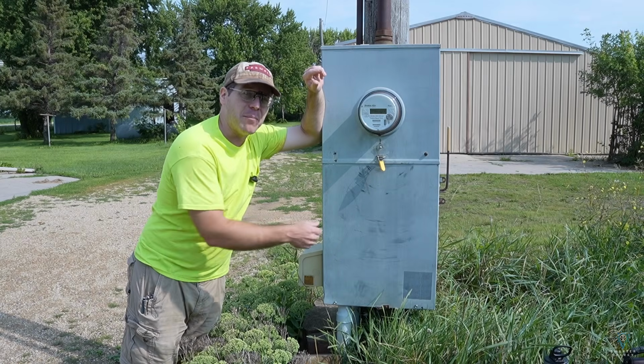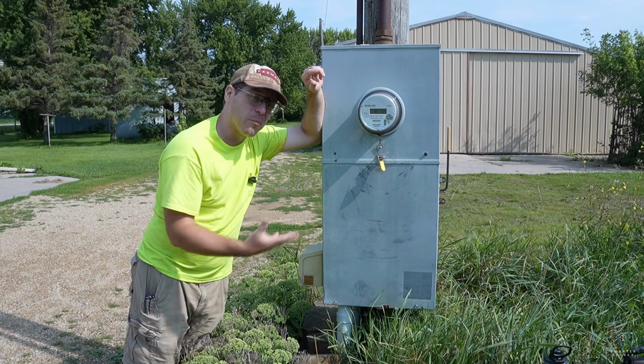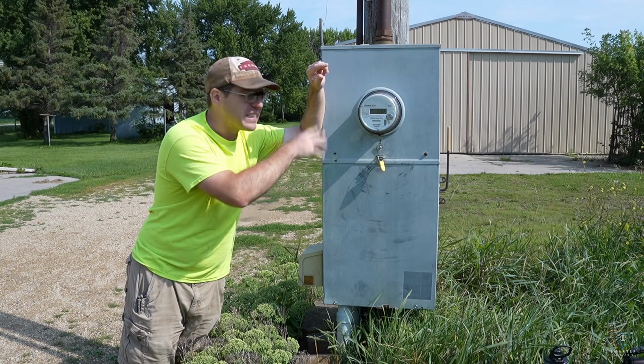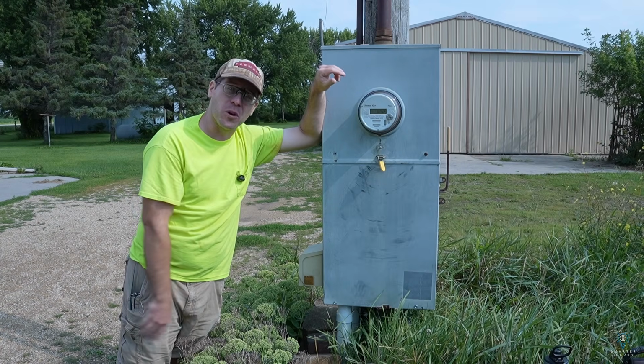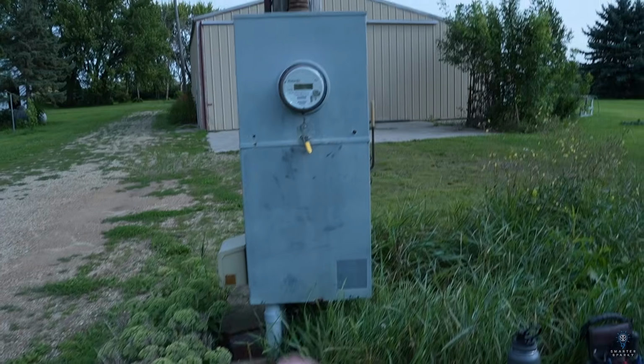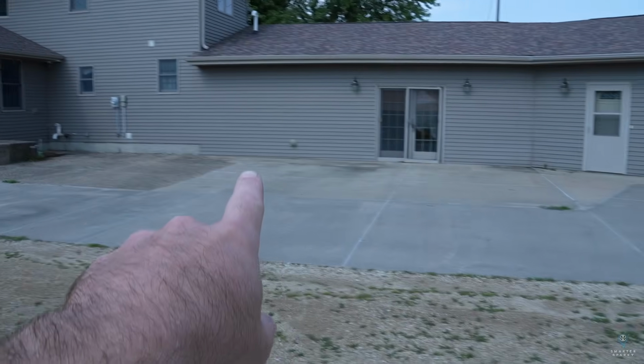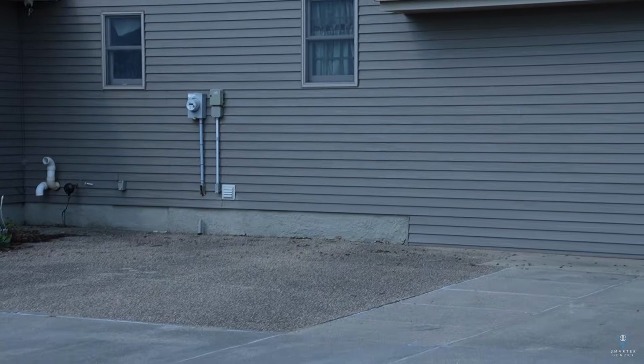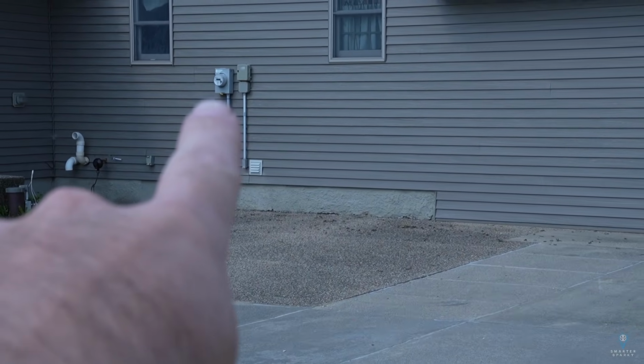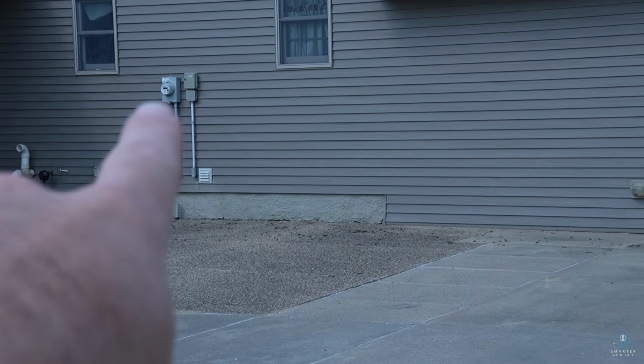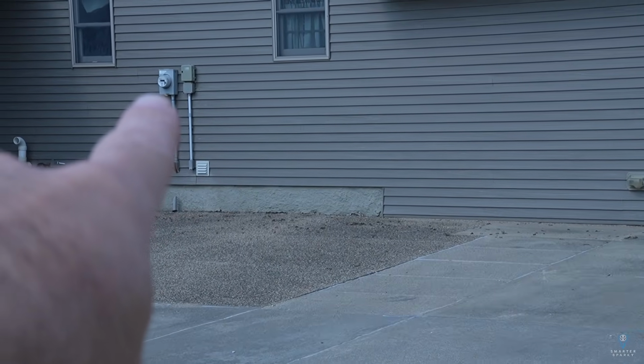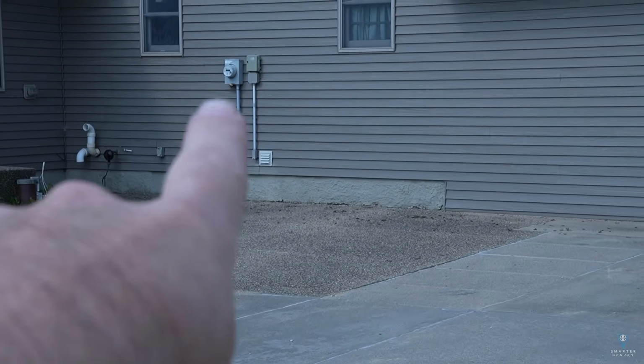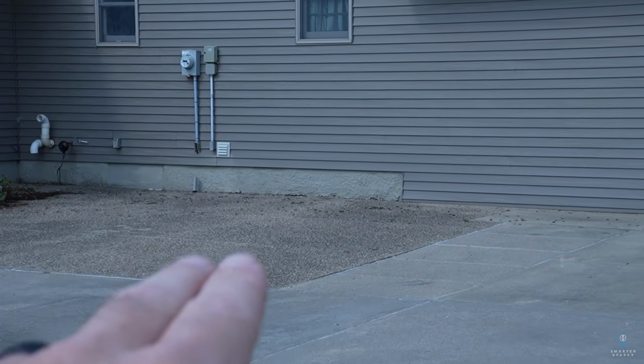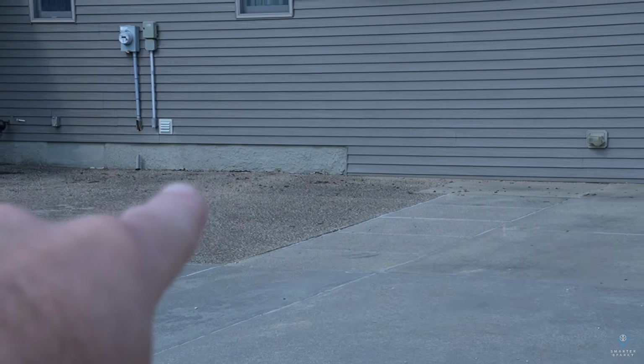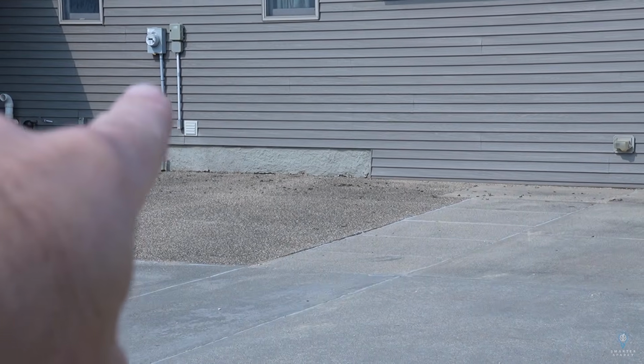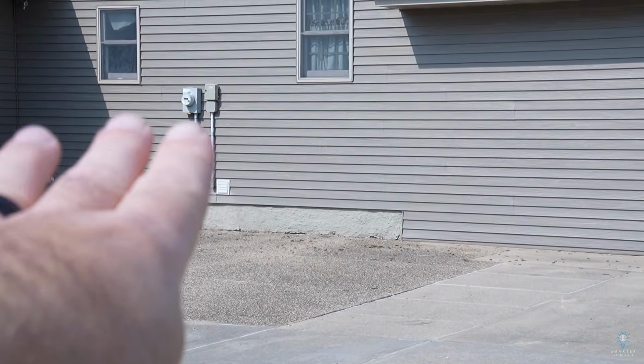So I haven't opened this up yet. I'm either expecting to see a loose connection on that neutral in here, or maybe even a corroded wire. This distribution panel is getting a little old, a little outdated. Someday I would like to do a service upgrade, but this has been working fine for now. Maybe that's going to change. We're about to find out. So again, we're coming from this panel and it goes underground all the way to the house. So the house panel is actually in the basement right about there. Now there is another meter on the house, and what that meter does is it just measures how much just my furnace and heat pump use, and I get a special rate on how much that uses. But the power company can also turn the air conditioner off if they need to on peak usage days. Otherwise, the actual incoming power is underground right about here and goes in right into the back of the panel. That second meter just measures right off of the first panel. That actually feeds that whole second panel that was next to my main panel.